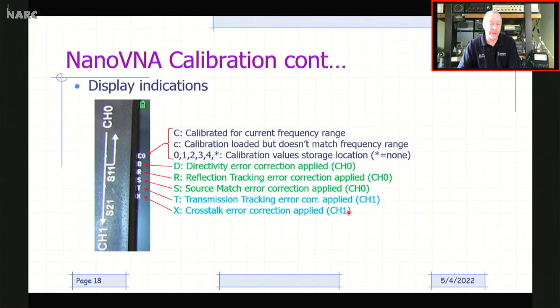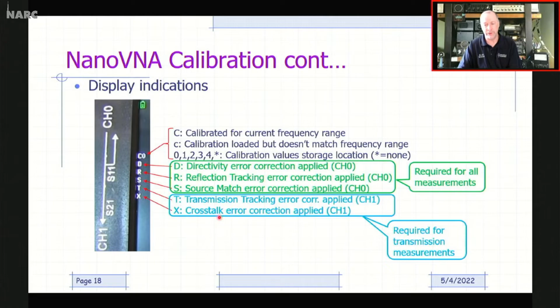The last 2 are calibrations that are associated with the transmission properties. And this would be crosstalk between the 2 ports, as well as transmission tracking of the measurement receiver on port 1. These are important when you're making measurements on channel 1, where you're making a 2-port measurement. These 3 are required for all measurements, whether you're making reflection measurements or transmission property measurements. You need to have these calibrations done. These last 2, which are really done by doing an isolation and through measurement, are only necessary if you're making transmission measurements. If you're just measuring VSWR of an antenna, you really don't have to do that last calibration step that takes care of these error corrections.